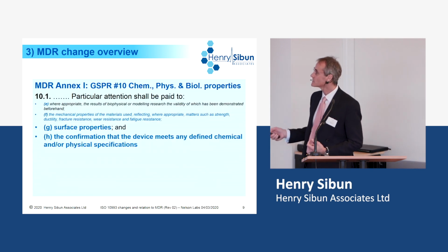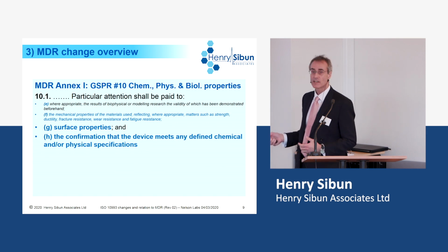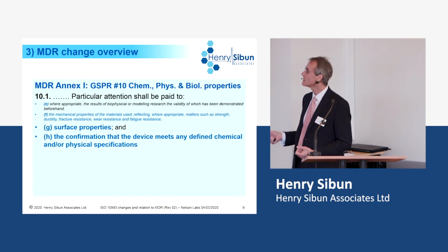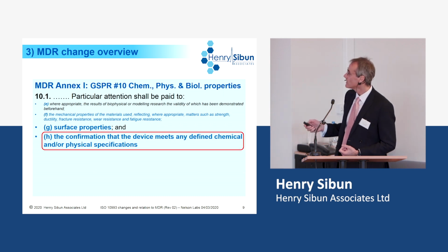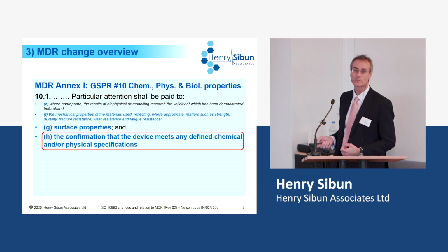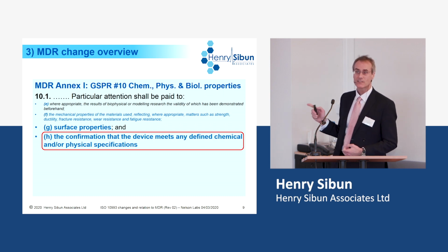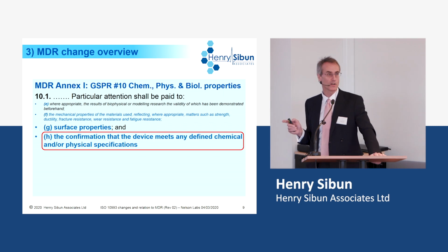Surface properties now specifically mentioned. Again, really not new for implants in particular. And then we've now got this one, which I think is more significant. So we've got confirmation the device meets any defined chemical and or physical specifications. And I think that does introduce some new requirements or at least new expectations.